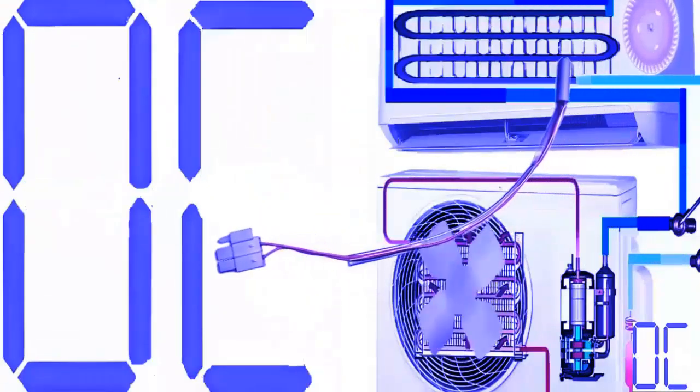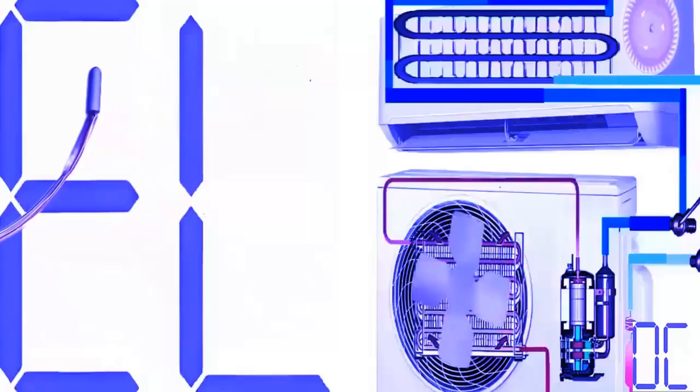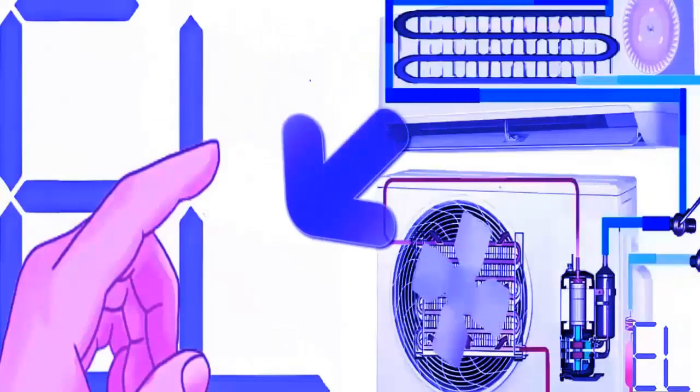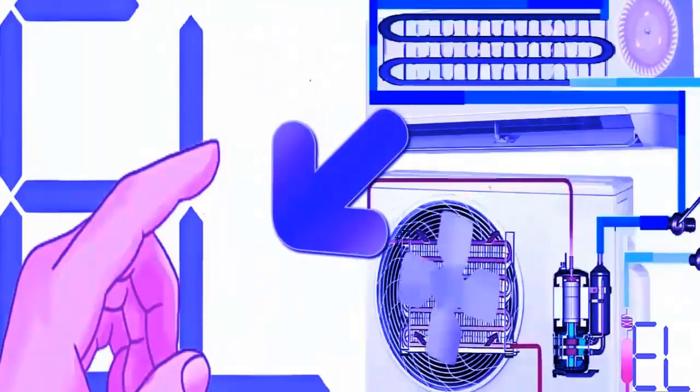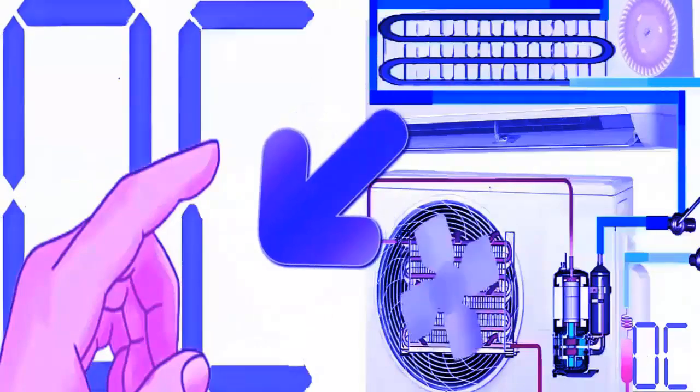9. If the error persists, consider replacing the sensor. If the issue continues, the problem might be with the electronic board. 10. If the air in step 3 is not sufficiently cold, there might be a refrigerant gas leak. Look for oil stains on the pipes connecting the indoor and outdoor units or on the coils, as oil often indicates leaks.